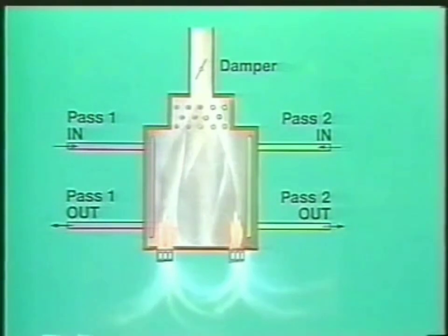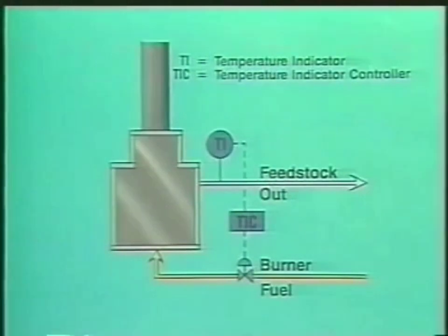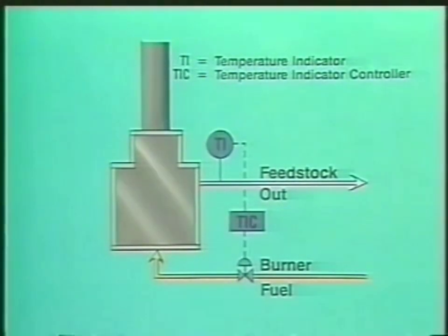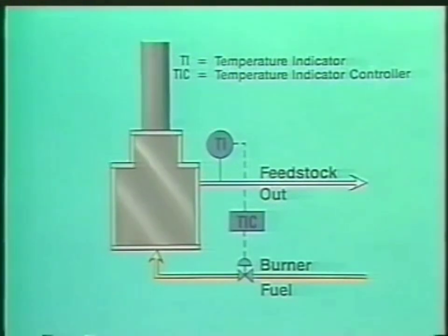After circulating through the tubes of the furnace, the feedstock is rejoined at the outlet. There is a target outlet temperature for the process flow, and this is used to determine the amount of fuel going to the burners. In an automatic control scheme, the outlet temperature is monitored by a temperature controller which controls the flow of fuel to the burners.